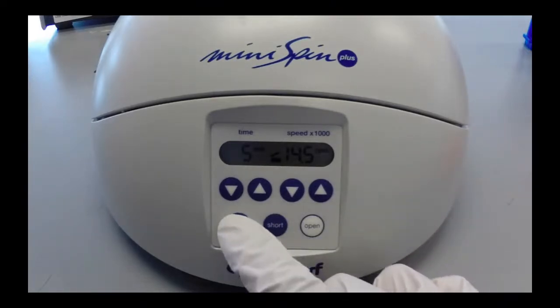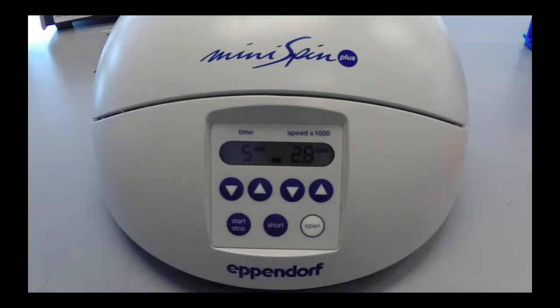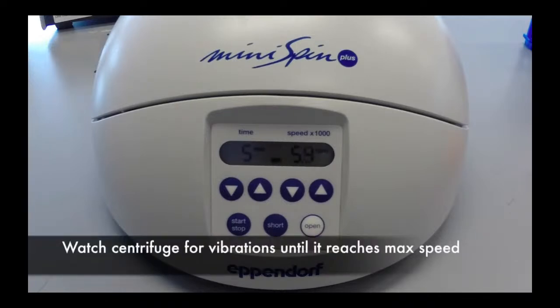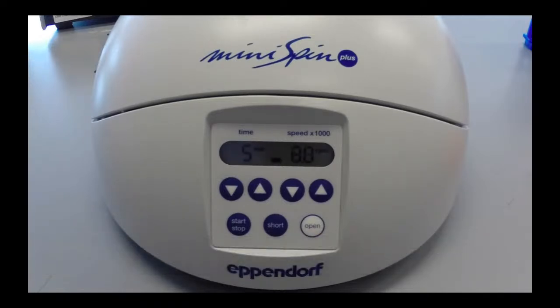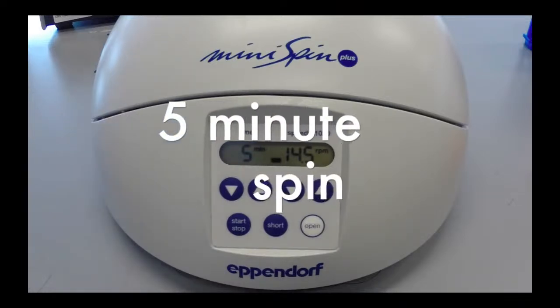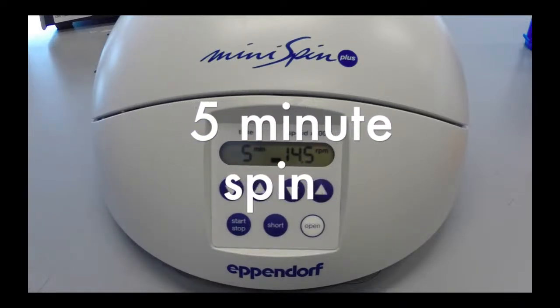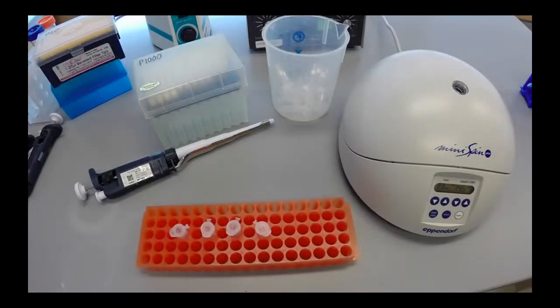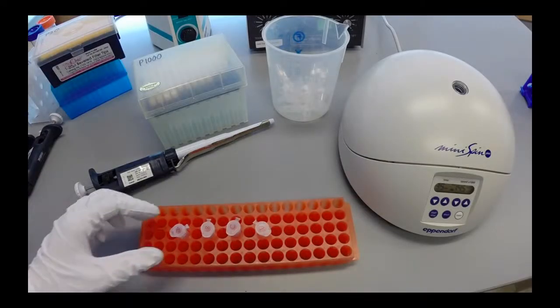The centrifuge will begin to spin. It is suggested that you watch the centrifuge until it reaches maximum speed to ensure that there are no violent vibrations, which may mean that the tubes are unbalanced or the internal lid has come loose. If this occurs, press the stop button immediately. As the spin is going, obtain 4 new tubes and label them.